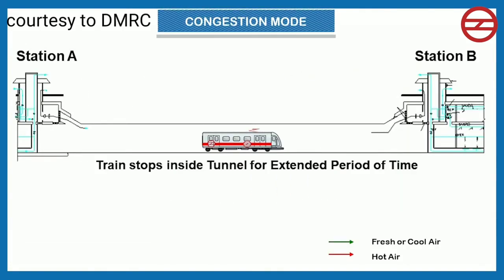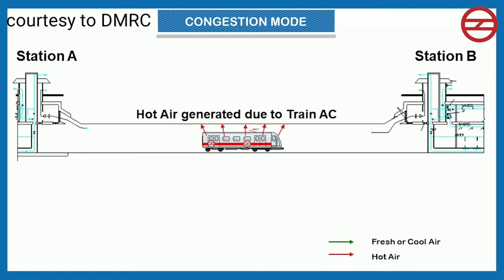Second mode of operation is congestion mode. Congestion mode of operation of TVS is mode corresponding to situation when train stops between two stations for extended period of time in the tunnel. Now, trains are provided with air conditioning system for passenger comfort, which releases hot air outside. This will result in a slow and steady increase in temperature in the surrounding of the train. When the tunnel air temperature in the vicinity of the train AC exceeds beyond a limit, the AC units will trip, causing discomfort to passengers.